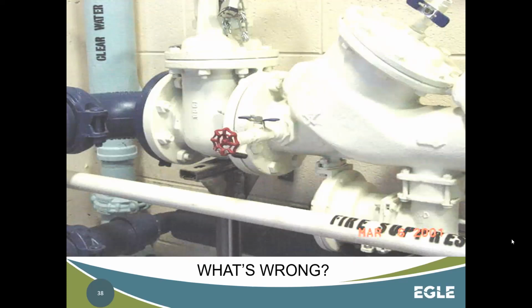Normally, you would expect to see some of these additional attachments on the RPZ or testable assemblies. There are test ports. What happened here is someone actually took one of those test ports and swapped it out for a hose bib.